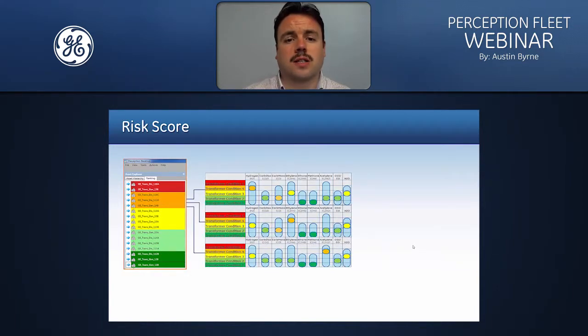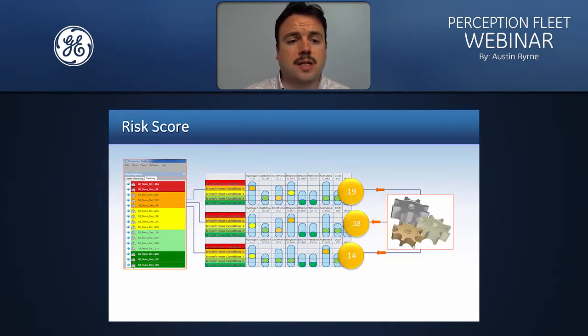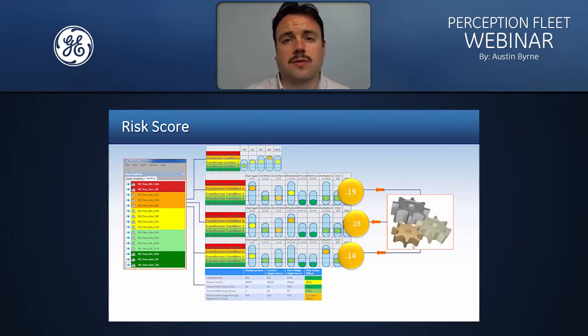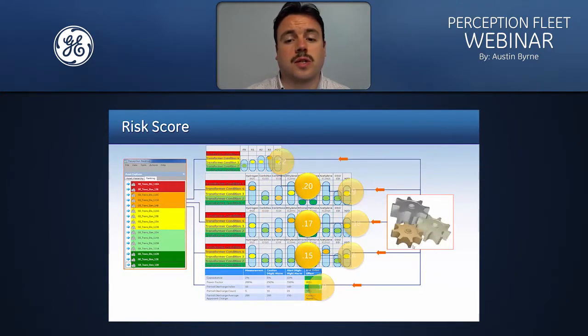So the risk score is calculated by taking all the results from the algorithms for the assets, we run them through the analytics engine, and we come back with a risk score. If any new analytics are applied to those assets, so for example, if you add a bushing monitor onto the transformer as well as the DGA monitor, then they will also have their own separate risk score, but that will directly impact the final risk score of the asset, so it will adjust the risk score. So you can see the example here on screen. So we're always aware of which asset is considered to be at highest risk.